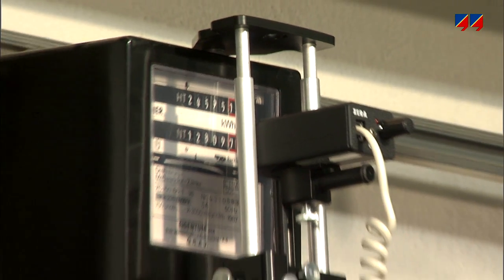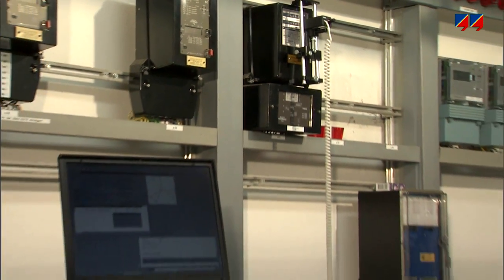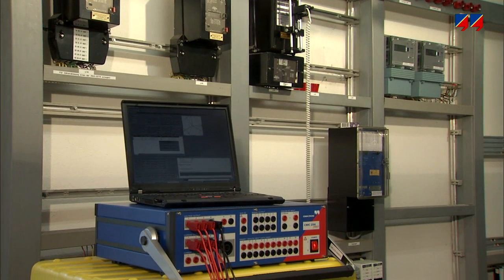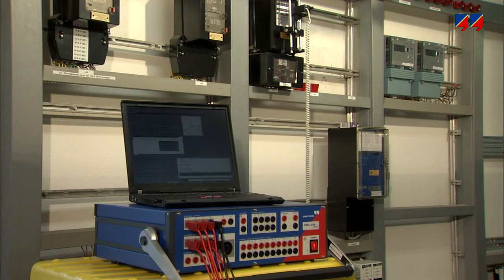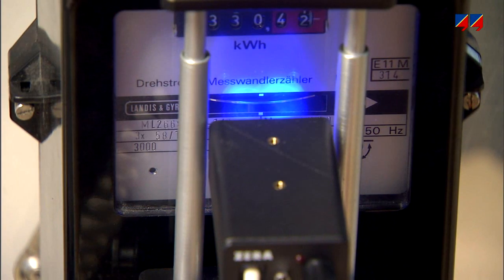All common types of energy meters can be tested. With special inputs for registering meter pulses, the CMC allows for closed-loop testing. These inputs, or the alternative optical scanning heads, allow the CMC to pick up all kinds of meter pulses, such as LEDs, Ferraris discs, or directly from mechanical or TTL outputs.